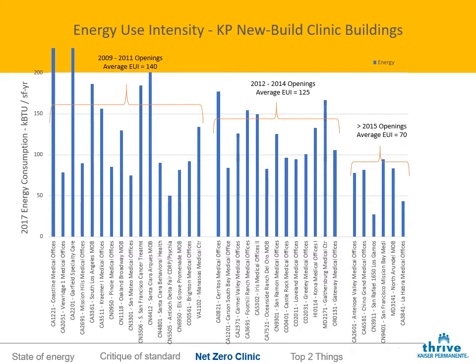The glass half empty part of this slide is that our energy target was 50. And the energy models for these buildings usually said they were going to beat 50. We had energy models that said they were going to be 45 or 40 or even 37, and our average came in at 70. So we have a lot of 40 and 50 EUI buildings that didn't actually reach 40 or 50 EUI. Well, that sucks, right? Because we need to learn from that. We need to improve our energy modeling predictions. We're routinely way off on natural gas, by the way. So we actually need to bridge that gap.